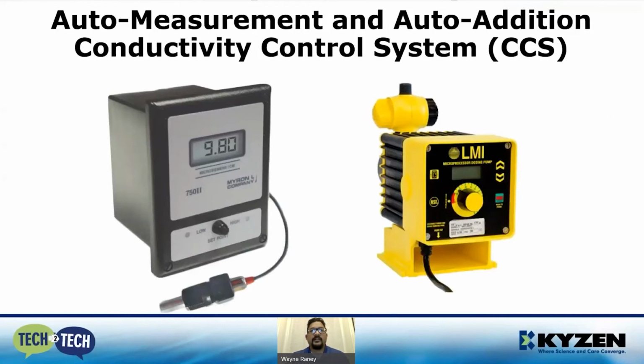The conductivity meter will read the actual conductivity and convert this to a 4 to 20 milliamp signal. It outputs this to the metering pump. The pump compares the current value to the set point, which is preset internally at KYZEN before shipment. It's important to note that the CCS only adds chemistry and that water additions should be made automatically by the washer.